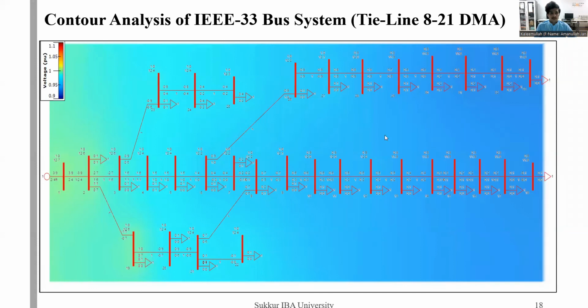Now, this is the analysis of the IEEE 33 bus system in which we have connected a tie line from 8 to 21 using the direct method average value. Here we can clearly see that the voltage profile is improved, due to which the power losses in the network are reduced. So this is the basic function of reconfiguration. By reconfiguration, we can reduce the power losses in the system, and we increase the voltage profile of the system.